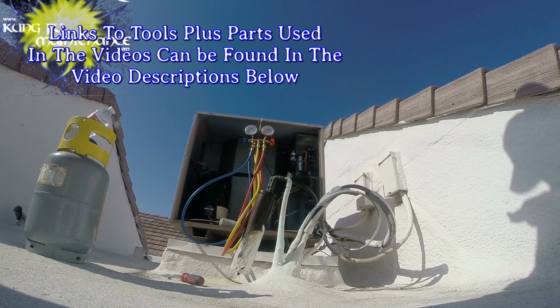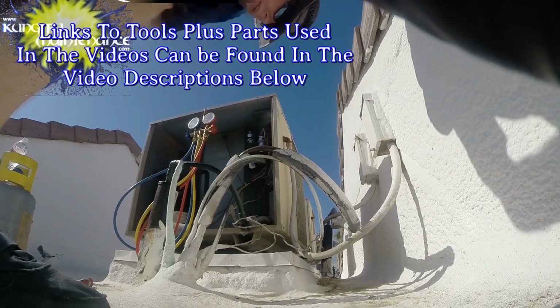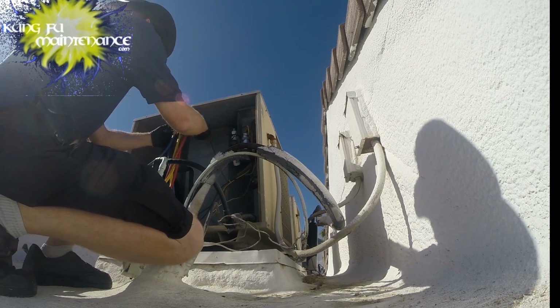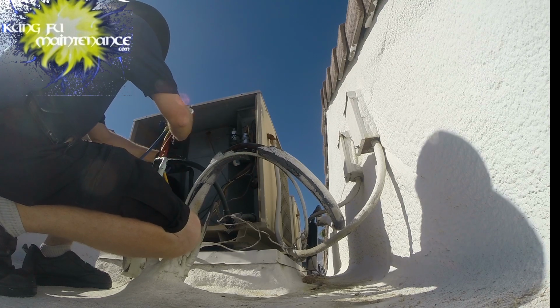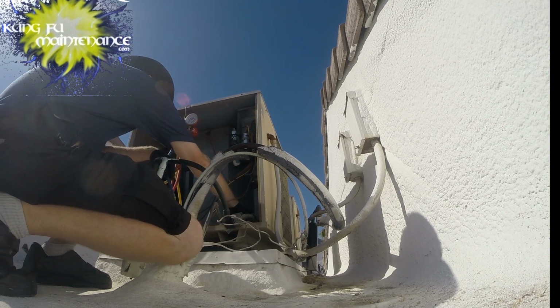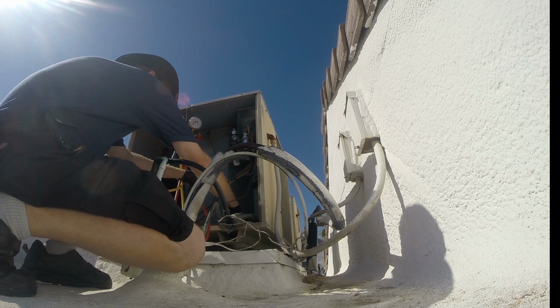combination is you want to let the unit run 5 minutes to get an accurate measure. Also, I brought my recovery tank because I think I'll be recovering a bit of refrigerant. But when you're recovering, we don't want to recover a whole unit with running the compressor because we don't want to take out the oil from the compressor. This one, I will need to recover a little bit of refrigerant.